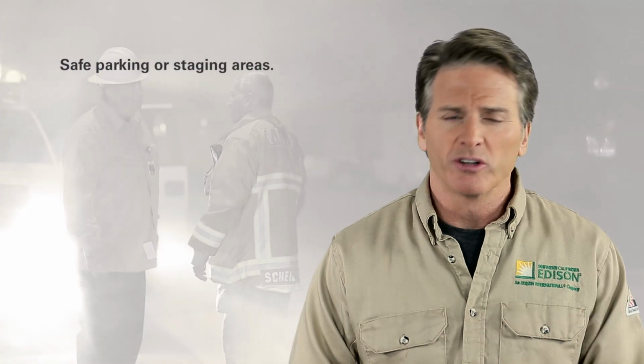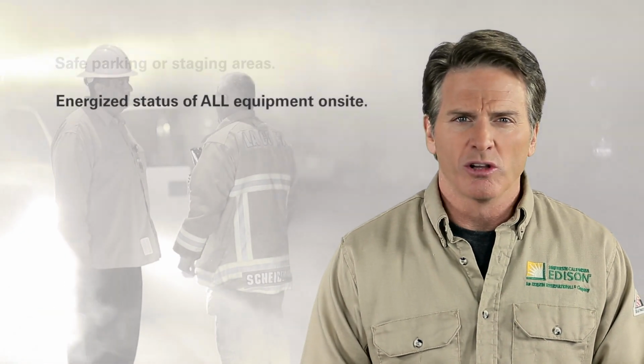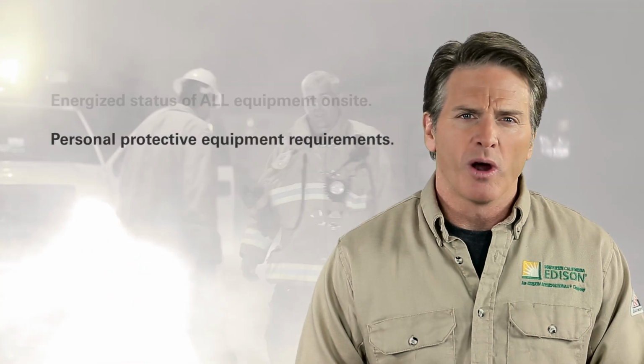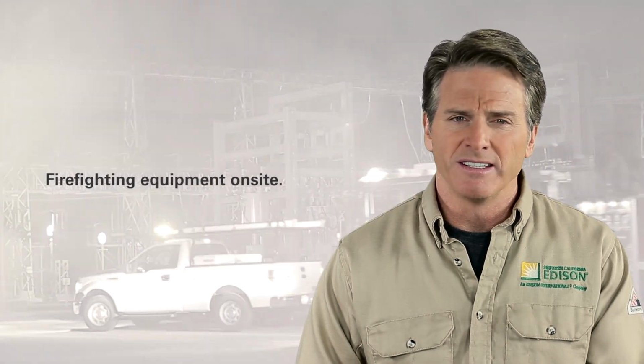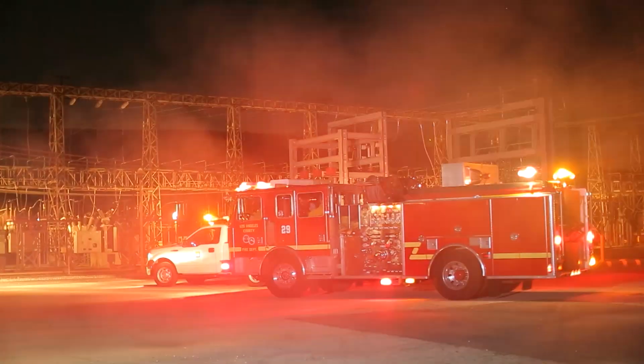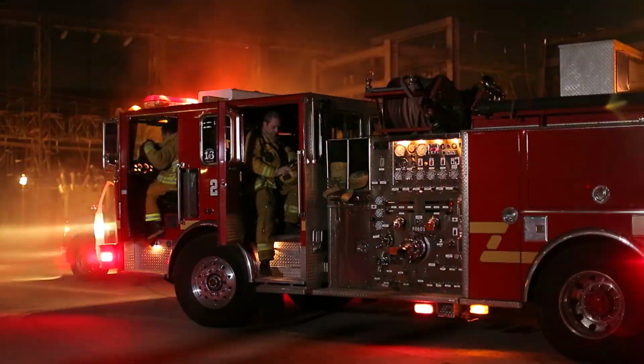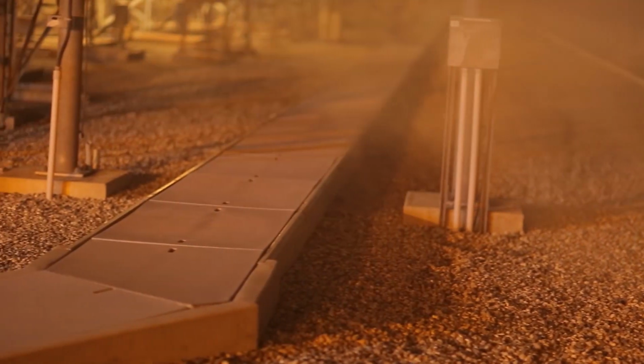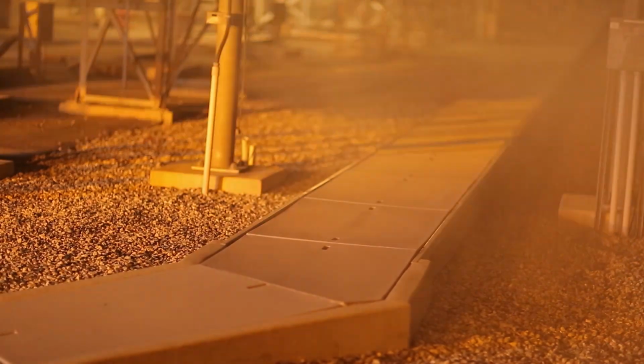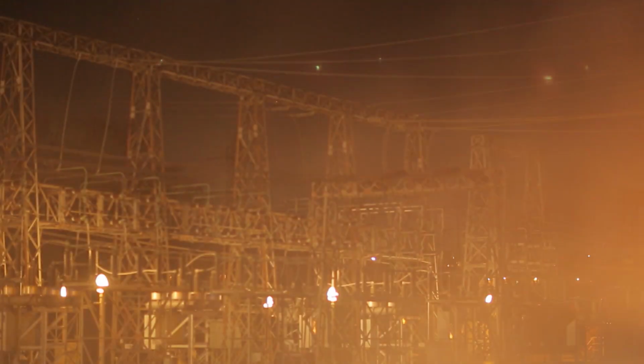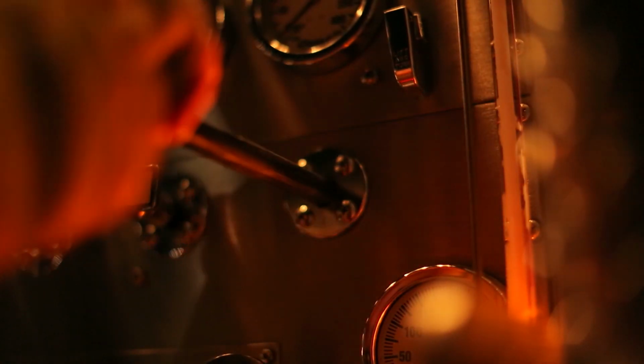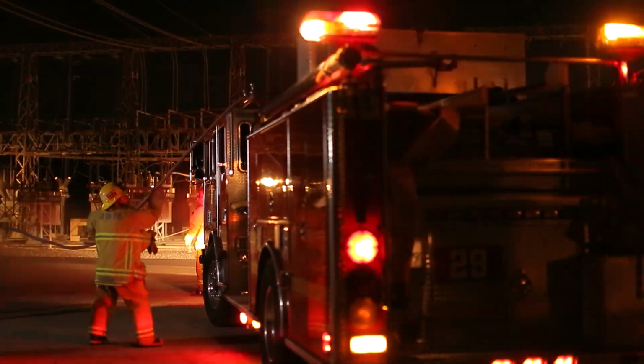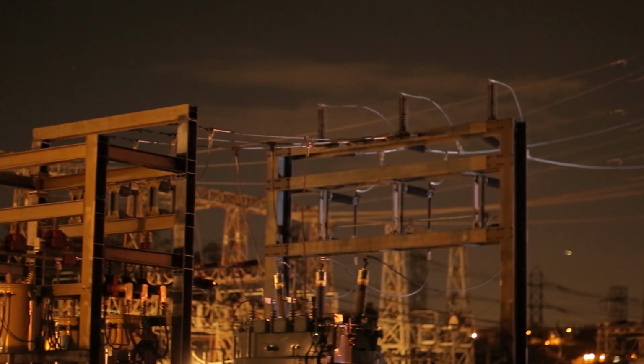Prior to any firefighting or rescue operations at a substation, consult our on-scene qualified utility workers to determine safe parking areas for equipment, the energized status of all equipment on site, personal protective equipment requirements, and whether or not firefighting equipment exists in the substation. Be aware, once de-energized, mineral oil is a primary fuel involved in substation equipment fires. Cable trenches contain energized cables and can carry the burning oil to adjacent equipment. Provide early exposure protection to adjacent de-energized equipment and structures. Class B foam is the preferred extinguishing agent for substation equipment fires. Firefighting operations should only involve Class A or B combustibles after equipment has been de-energized.